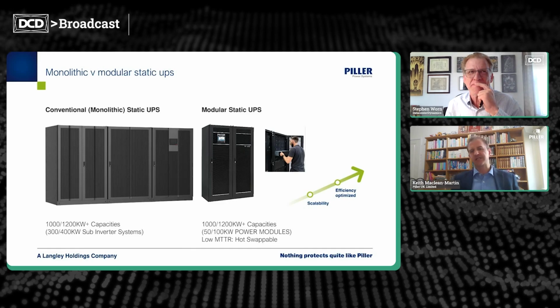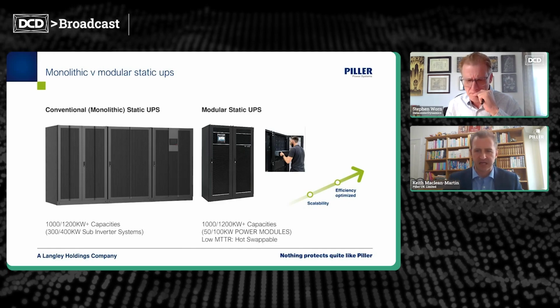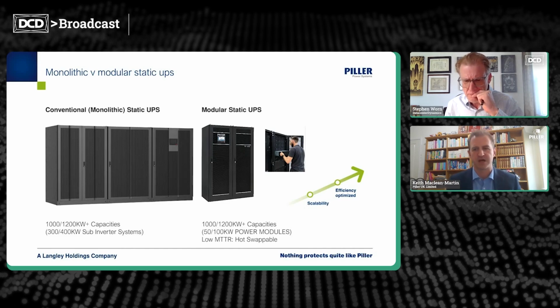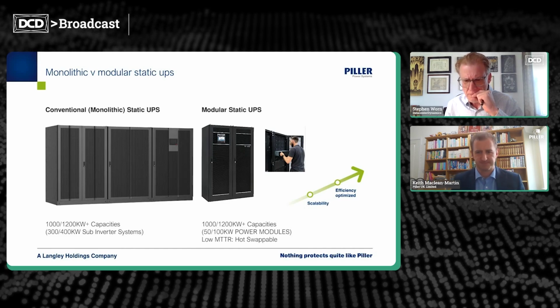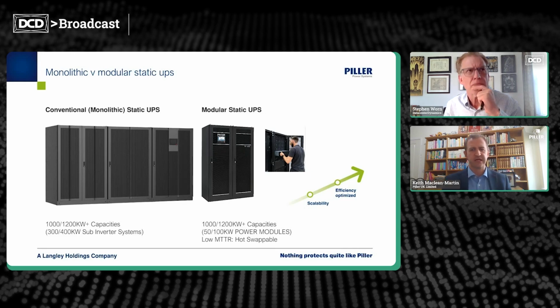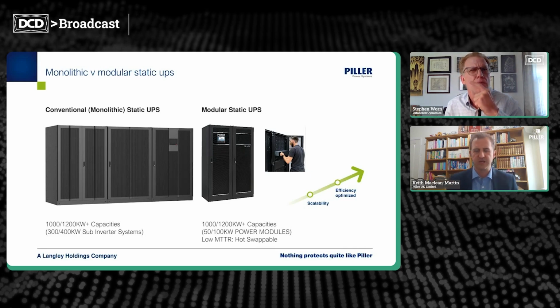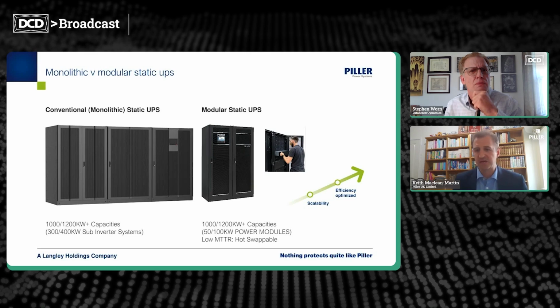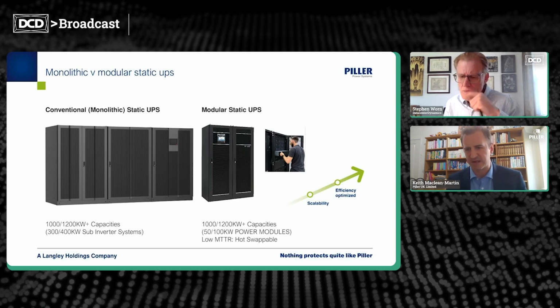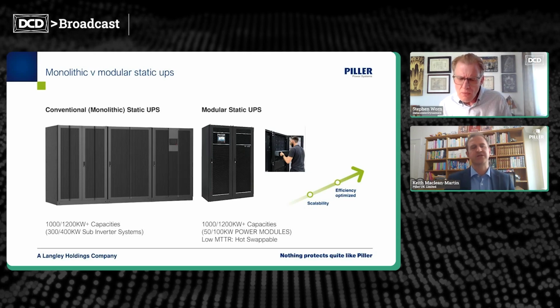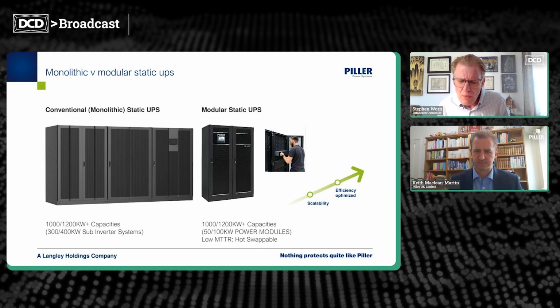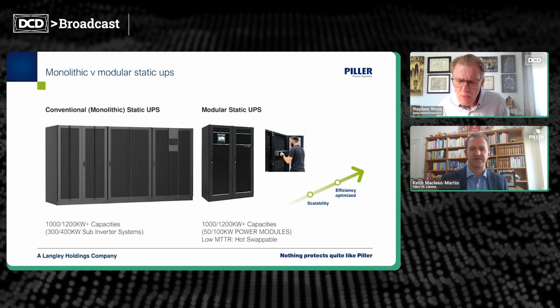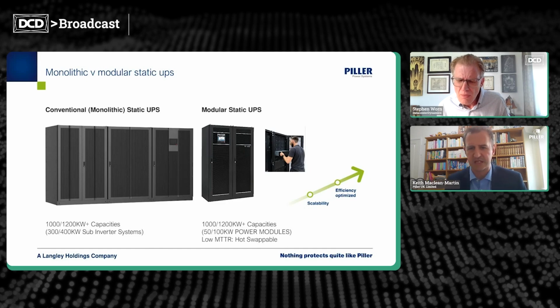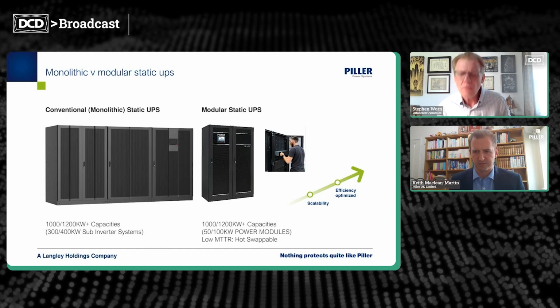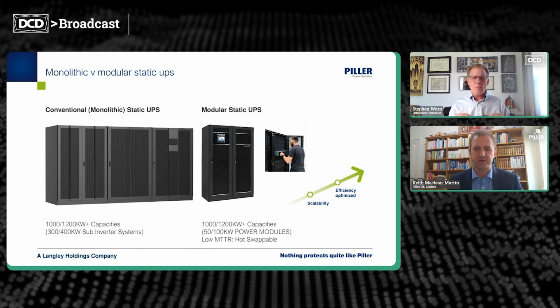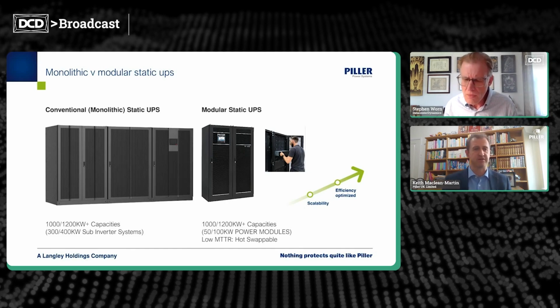Now, traditional data center load profiles were somewhat steady state, with only significant step changes introduced during infrastructure failures. However, the AI compute demand is facing more volatile and more frequent load changes caused by the load alone, not by these failure events. And this in turn is stressing static UPS components more. The use of modular UPS has the advantage of low mean time to repair, with all module assemblies being hot swappable. Therefore, a robust but also adaptive UPS system is preferable to meet those AI demands.